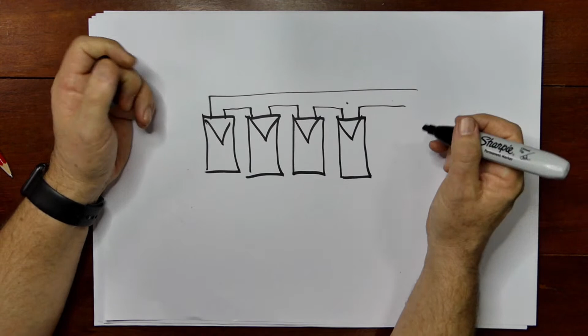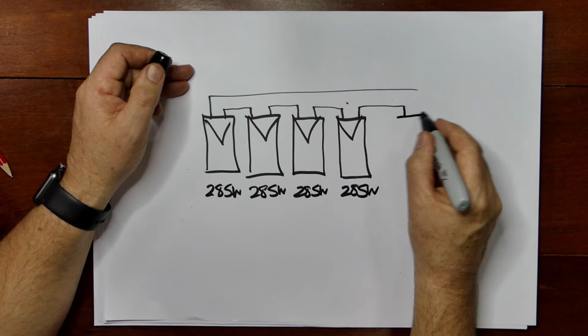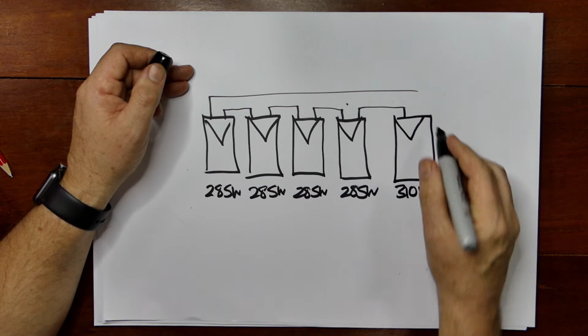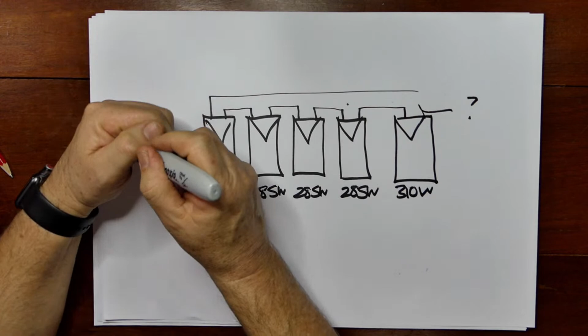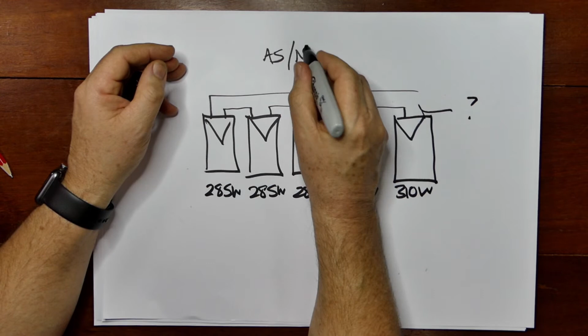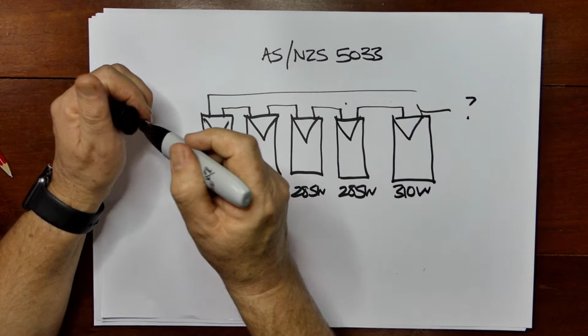Either one of them is faulty, or you want to add one more to the system. Can you just tack on another one that's a bit bigger - putting a 310 watt module on the end? Can we do that? Well, there's 2 considerations. Are you allowed to do it legally, like the standards - the standard for installing solar PV systems in Australia and New Zealand is AS/NZS 5033, the PV installation standard. It's for both on-grid and off-grid, basically just for PV systems connected to anything.